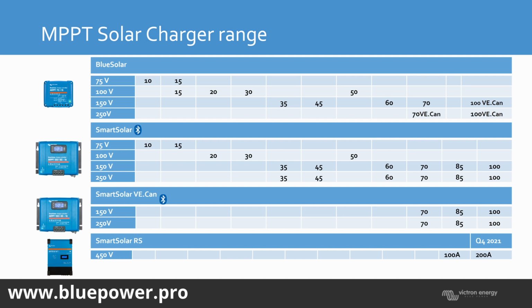On the units, the older ones don't have the VE.Can capability, and that's also marked on the part number. If the unit has VE.Can in the part number, then it's got the capability to communicate over the parallel bus of VE.Can. But if it's the older, standard BlueSolar or SmartSolar MPPT, then you're going to have to connect it with VE.Direct communication. And on certain GX devices, you've got a limited amount of ports for that as well. So do take note when you're building systems with these older MPPTs.